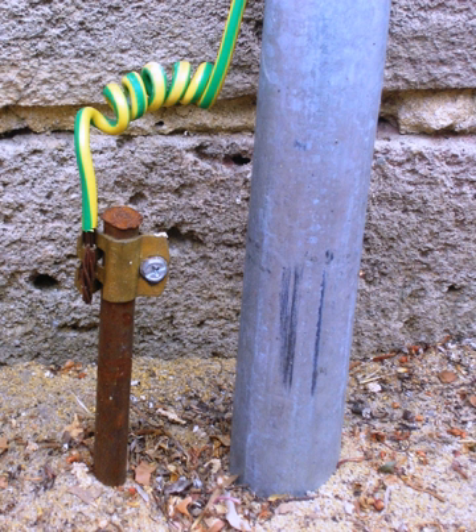In a mains electricity AC power wiring installation, the term ground conductor typically refers to three different conductors or conductor systems as listed below. Equipment earthing conductors provide an electrical connection between the physical ground, earth, and the grounding, bonding system, which connects, bonds, the normally non-current carrying metallic parts of equipment. According to the U.S. National Electrical Code (NEC), the reason for doing this is to limit the voltage imposed by lightning, line surges, and contact with higher voltage lines.